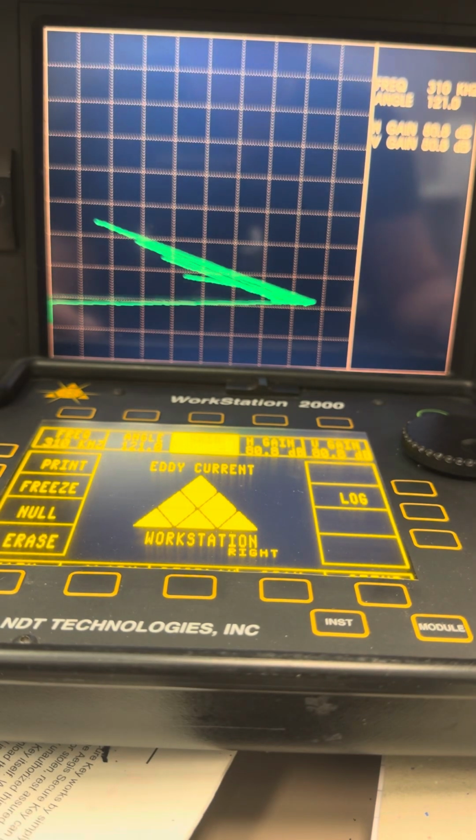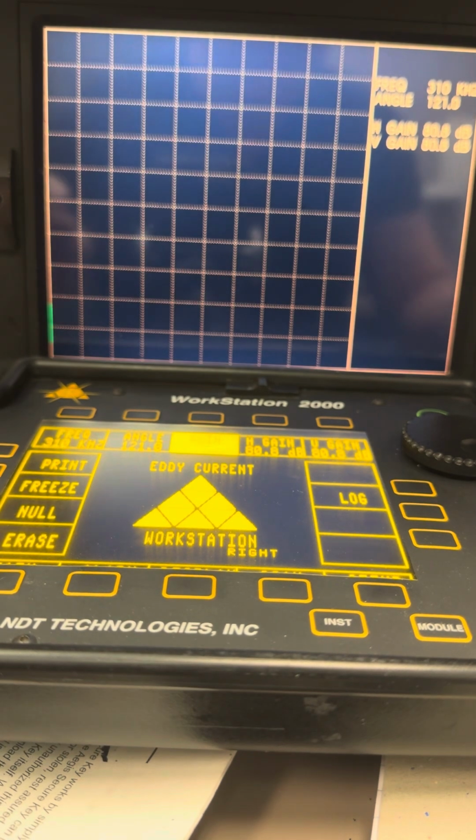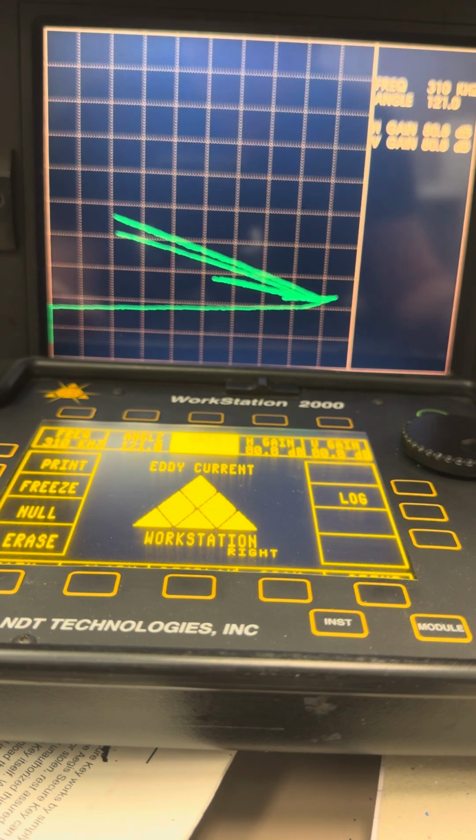And now I've got a fairly horizontal liftoff line, and I've got some good amplitude or voltage of the signal, so that's good. But maybe I want to give them a little bit more vertical amplitude. So what I'm doing is increasing the separation angle between liftoff and our signals of interest. Separation angle is something that you'll see when you're using the slide rule a lot.